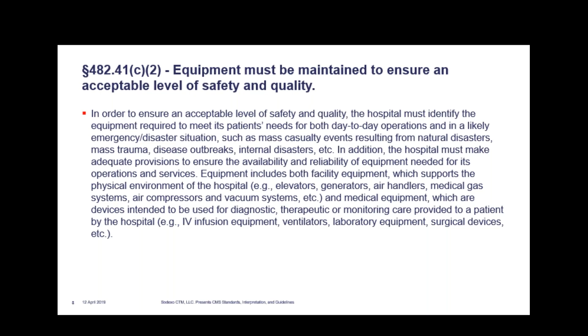All right, so all equipment must be inspected and tested for performance and safety before and after major repairs and upgrades. So every device you have on your inventory should have an independent inspection prior to placing it on any patient use. All equipment must be inspected, tested, and maintained to ensure the safety, availability, and reliability. A lot of these are going to sound very repetitive. I'm sorry, I'm not going to read them word for word. But the equipment maintenance activity must be conducted using hospital personnel, contract services, or a combination of both. Individuals responsible for overseeing and development must be qualified. And we're going to go into qualifications here shortly.